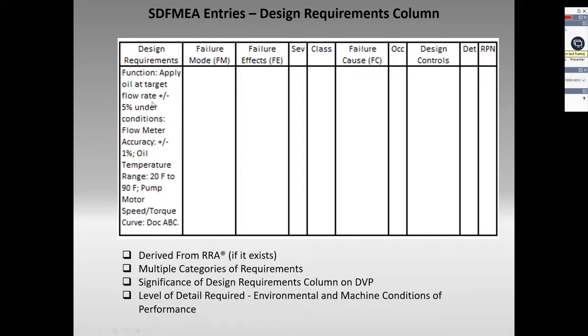Again, these design requirements have to be written to a level of detail that you can verify, both from your performance standpoint and also what we call the degrees of freedom. So when I run this particular test, I'm going to want to make sure—since I know this oil viscosity is going to change over this 20 to 90F range—that my software has the right algorithms to handle these variations.